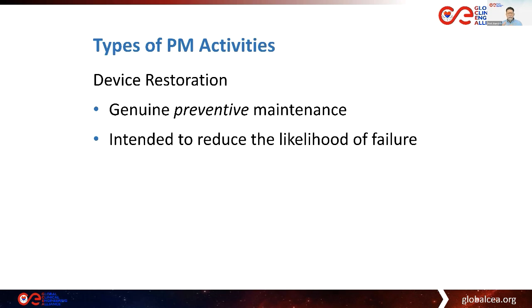So, for example, if we replace the battery on a regular schedule that is appropriate to the kind of device and the kind of battery, we make it less likely that the battery is going to fail when it's being used by a patient, by a user for a patient. So we're preventing problems by doing that advanced aspect of PM called device restoration.